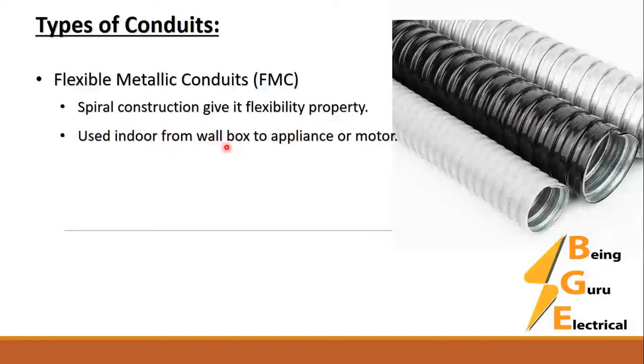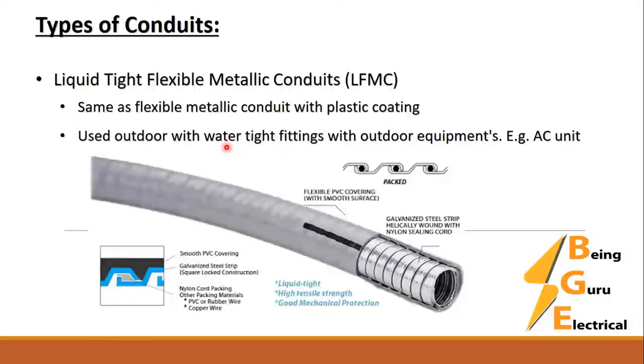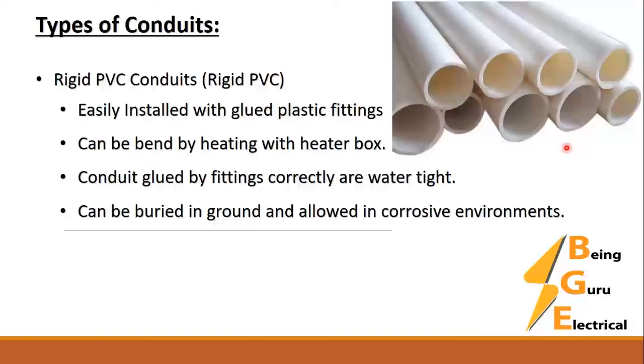Liquid-Tight Flexible Metallic Conduit, or LFMC, is the same as flexible metallic conduit but with a plastic coating. It is used outdoors with water-tight fittings and outdoor equipment such as AC units. Rigid PVC conduit is easily installed with glued plastic fittings. It is used inside concrete or walls, can be bent by heating with a heater box, and can be buried in the ground and used in corrosive environments.